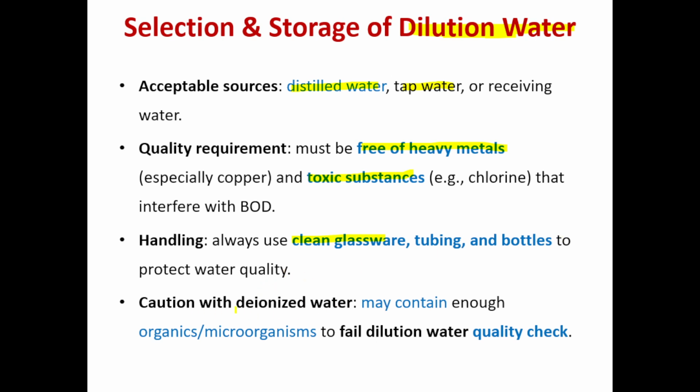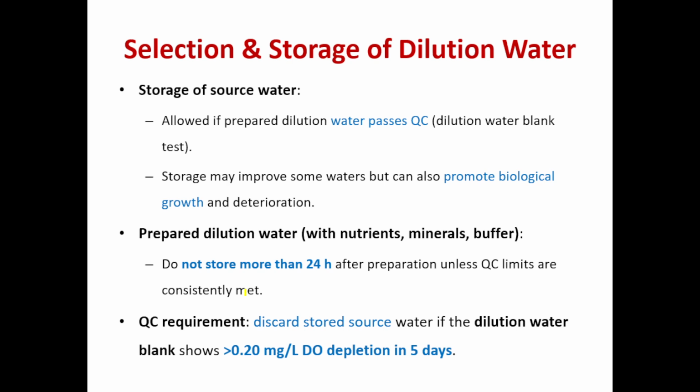In the case of deionized water, it may contain enough organic matter or microorganisms to fail dilution water quality checks, so we should be cautious if we are using deionized water. Now, the storage of source water. It is allowed if the prepared dilution water passes the quality check, so it's very important that dilution water passes the water quality checks. We will see water quality checks in later slides. Storage may improve some water but can also promote biological growth.